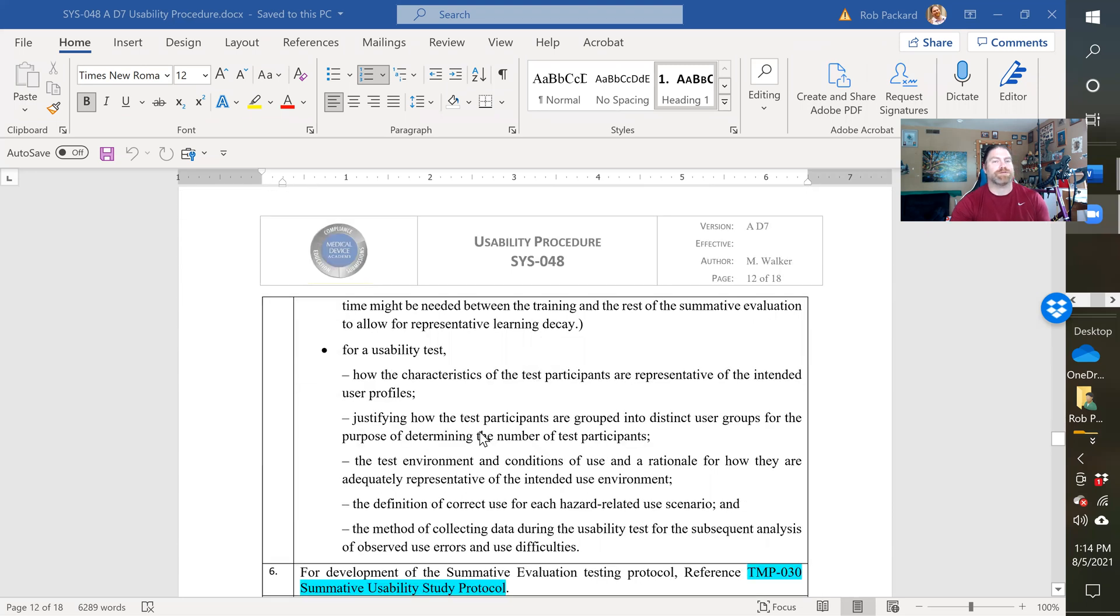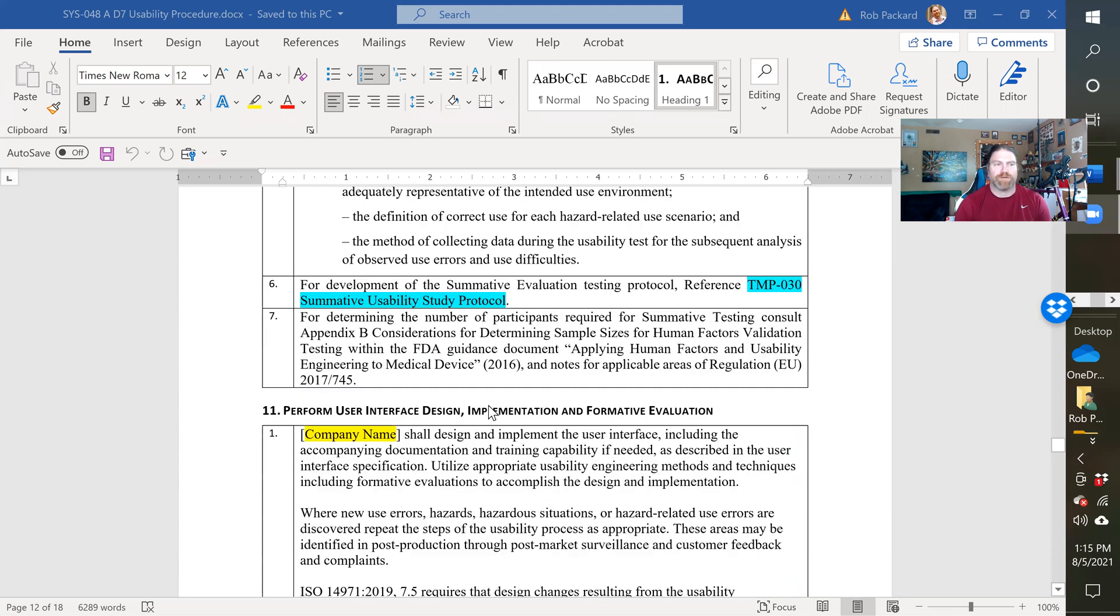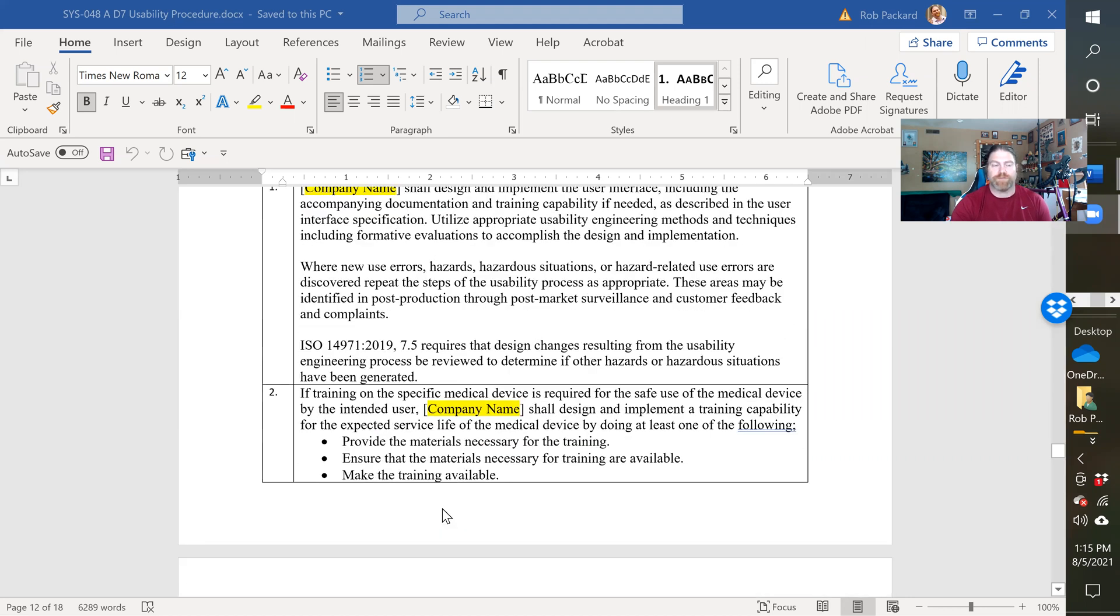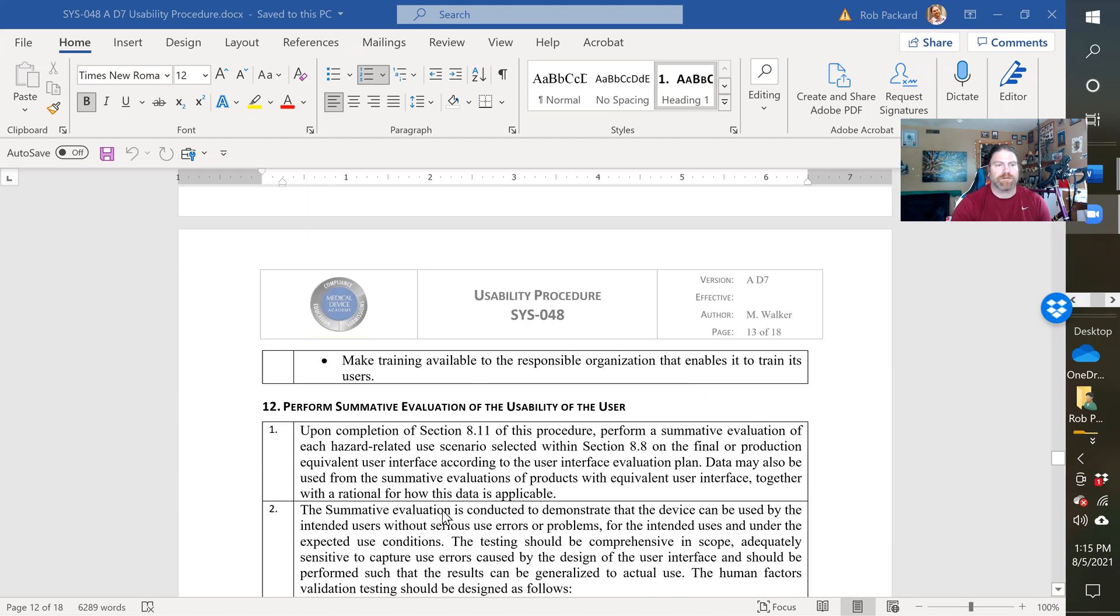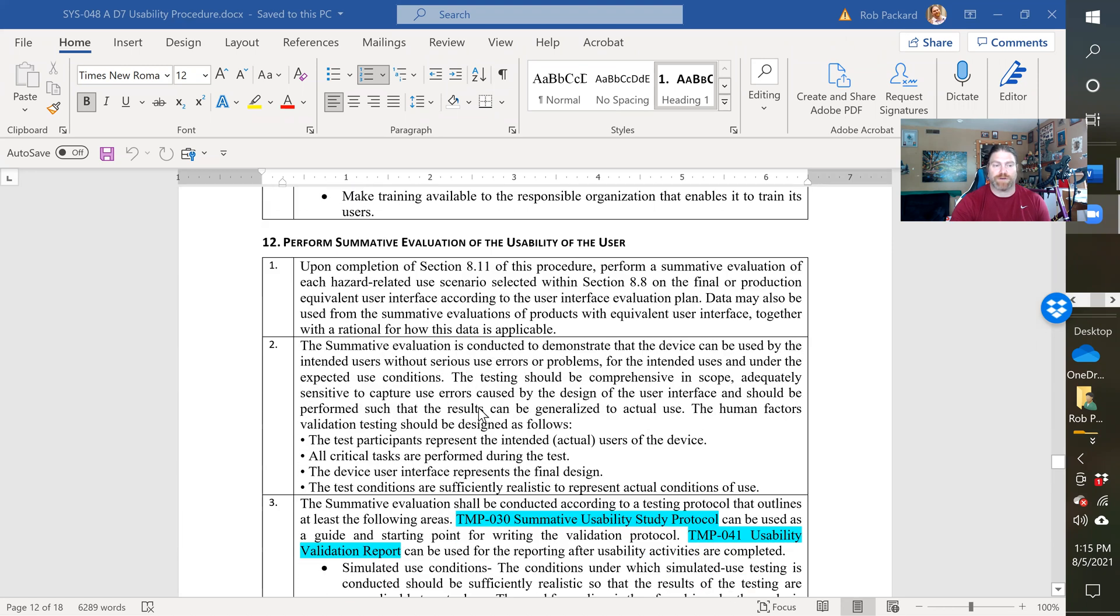And as I said, all of these are requirements we added to be more compliant with the IEC 62366, if you're CE marking. And then, how to perform the interface design and implementation for formative evaluations. This would be during your development phase. Performing a summative evaluation, that would be during your verification and validation phase.